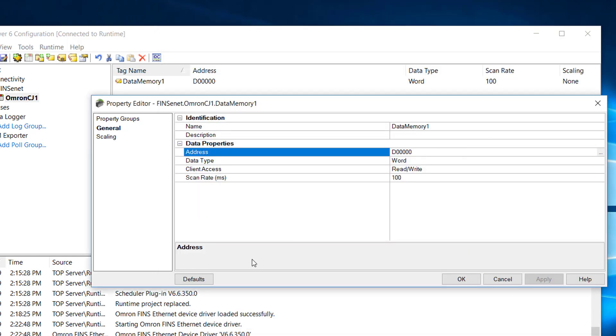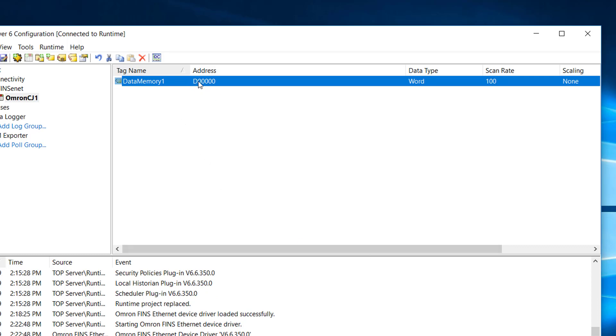It's a good way to know what your valid addressing is. You don't actually have to have a static address in TopServer — from Wonderware or other client applications, you could also specify a D0000 address with a data type appended, like D0000 at word, at string, or at float, using any of the supported data types from the help file, to access data dynamically without a static tag. That's it — it's relatively easy. If you were to configure one static address just for testing purposes, we do recommend that, because it allows you to launch the OPC Quick Client which will auto-populate with that static tag and show you whether you have good status and a good value, so you can test and make sure your channel and device properties are correct before configuring your client application.